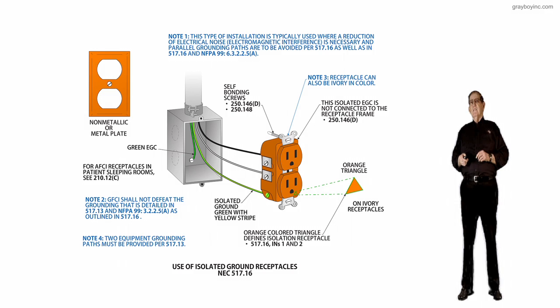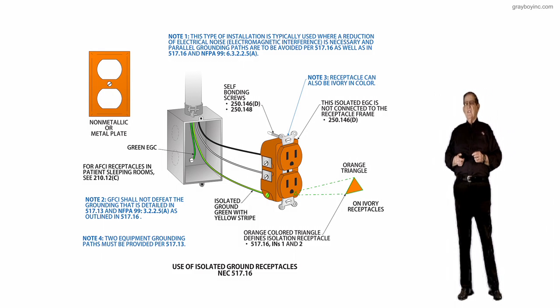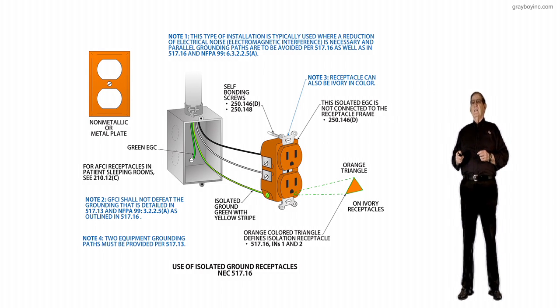When we review the receptacle itself and connect this isolation equipment grounding conductor, usually green with yellow stripe or stripes, notice it connects to that green screw that connects to the U-ground. If you connect any kind of sensitive electronic piece of equipment to it, it grounds the enclosure of the sensitive electronic equipment, the metal there.